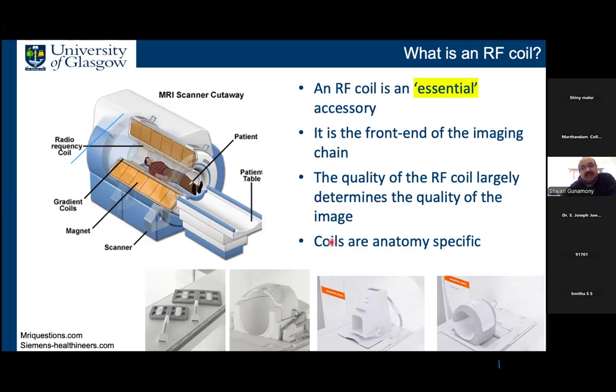And the coils must be anatomy specific for optimum performance. You have to have anatomy specific coils. So in the photographs here, you can see a list of coils. On the left, this is a general purpose flex coil, which can be wrapped around any anatomy of interest, but the image quality may not be the optimum. Here, this is a head coil from Siemens, and this is a coil for the ankle, and it's a coil for the knee. So these are anatomy-specific coils.